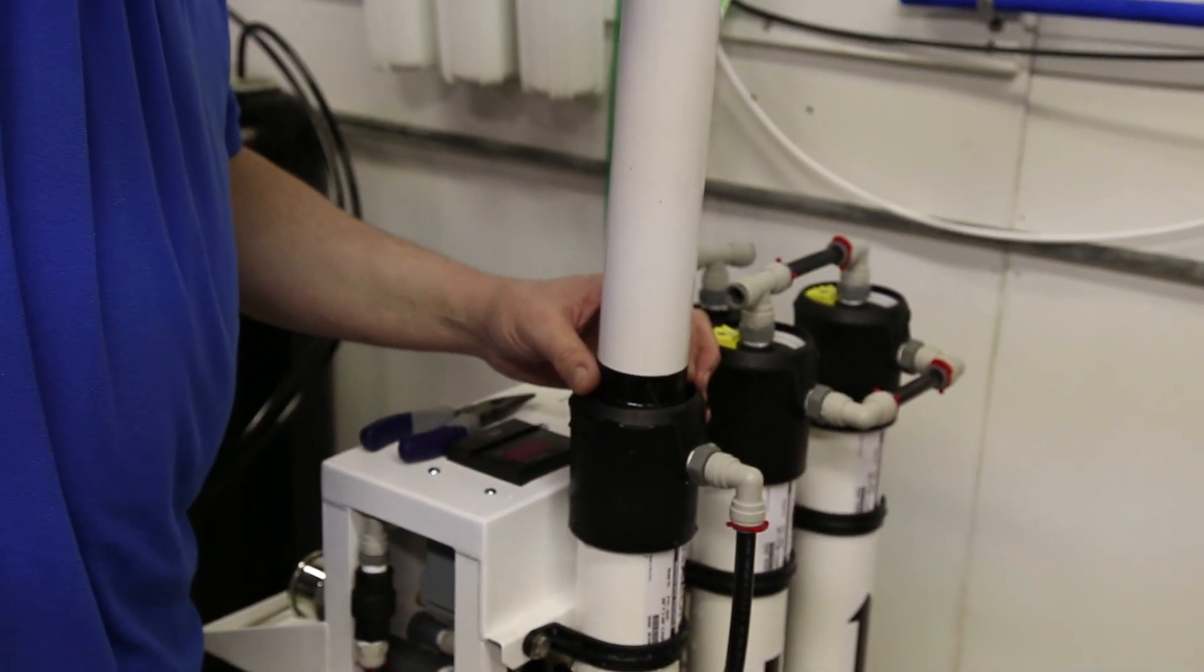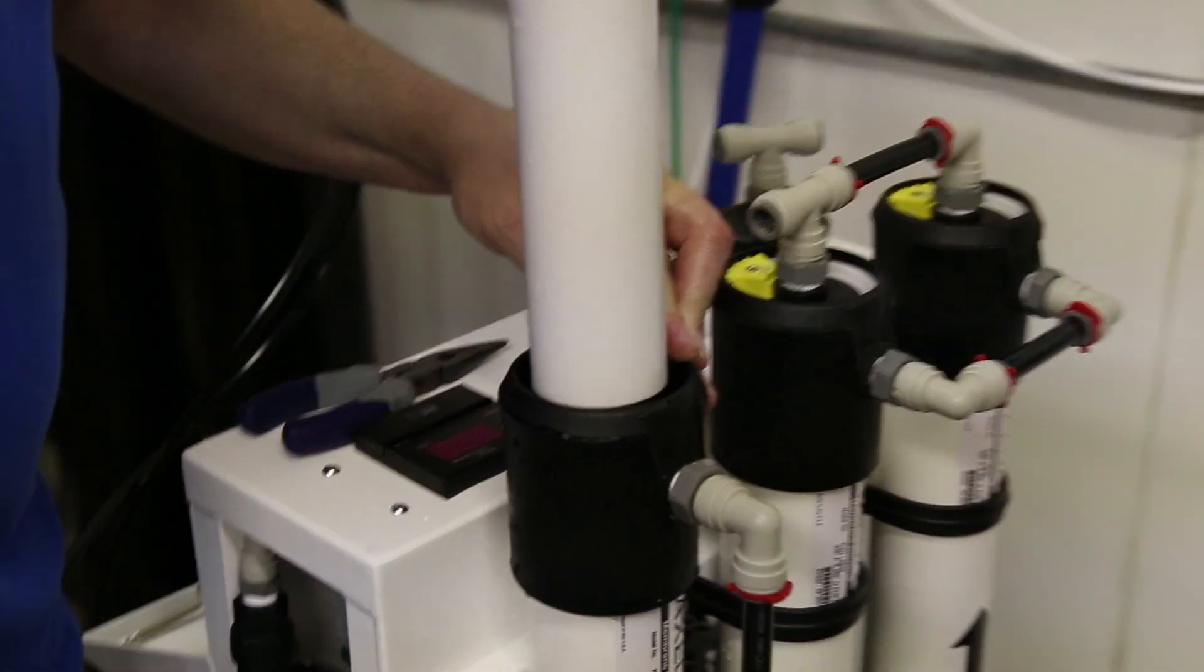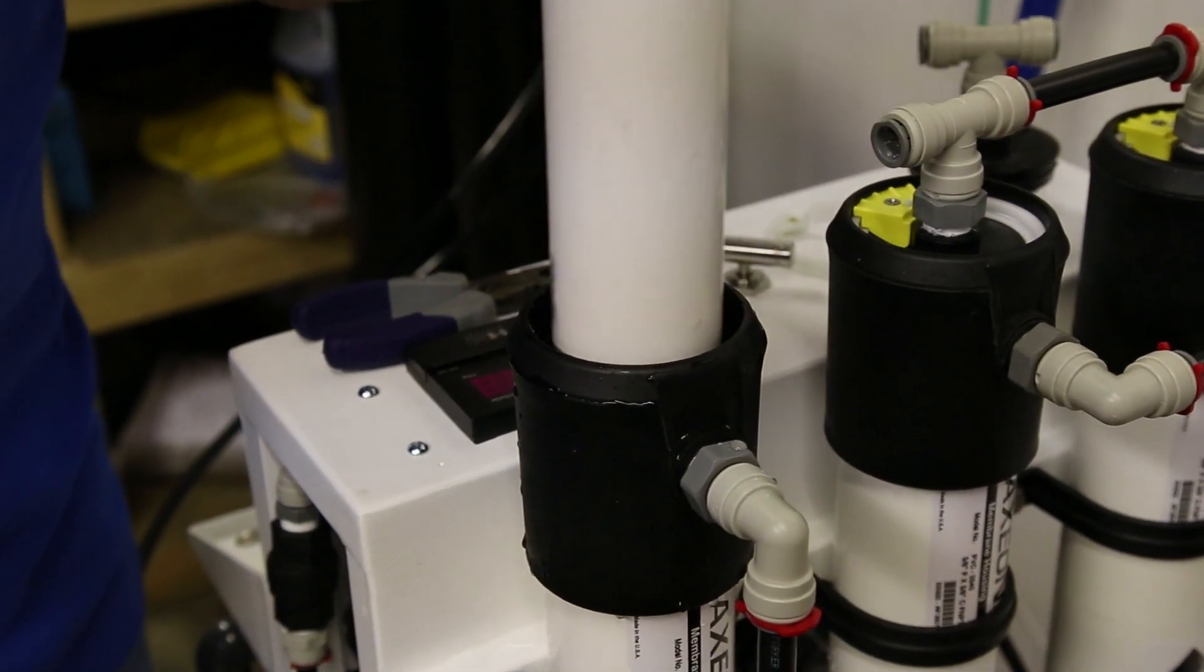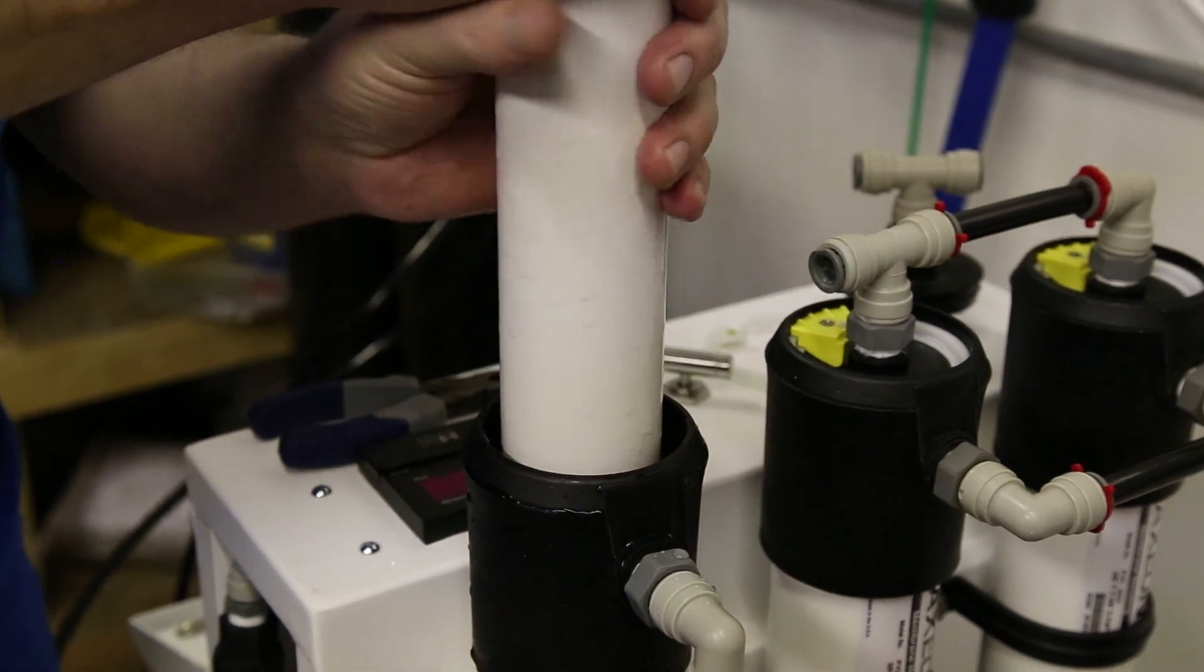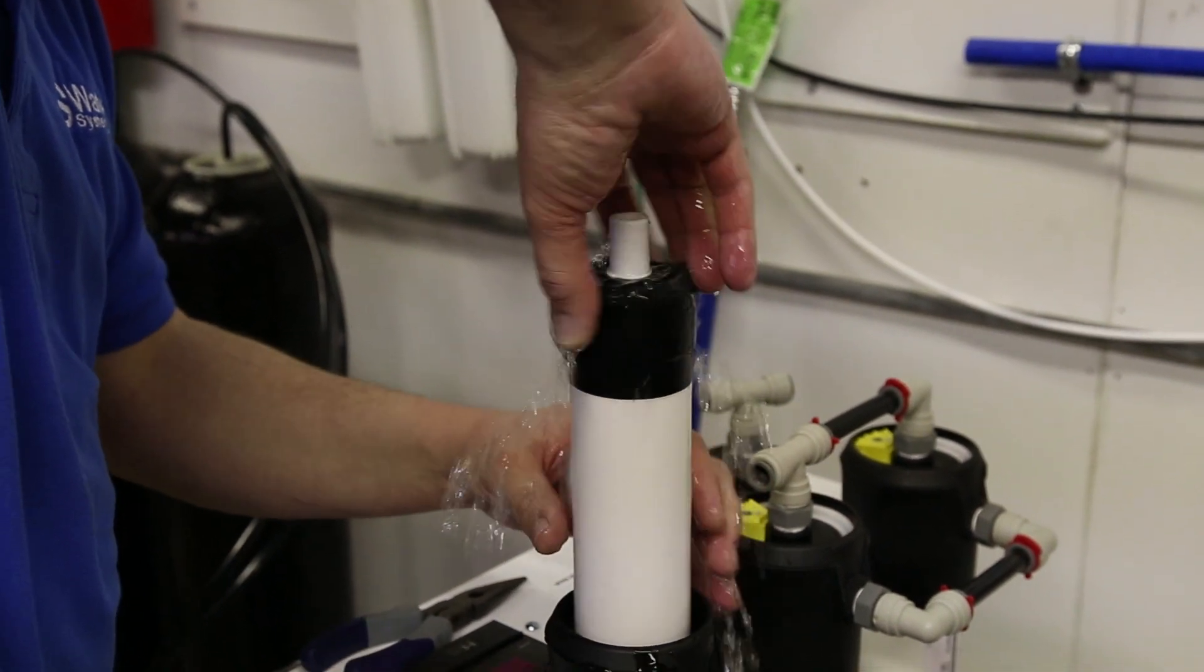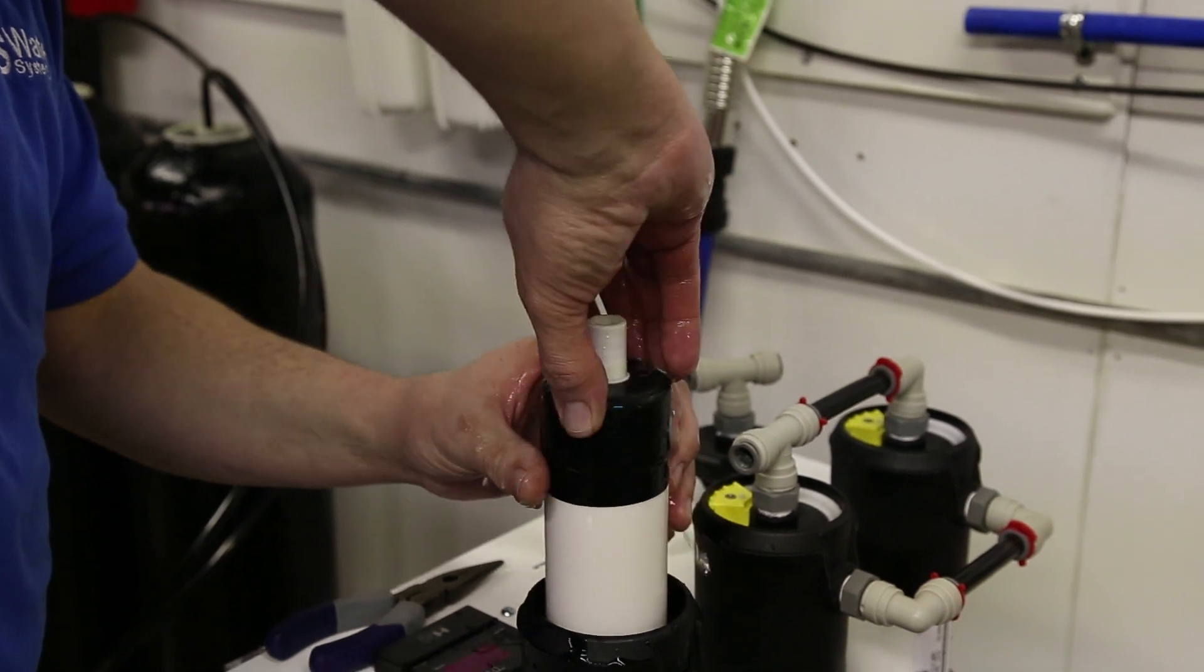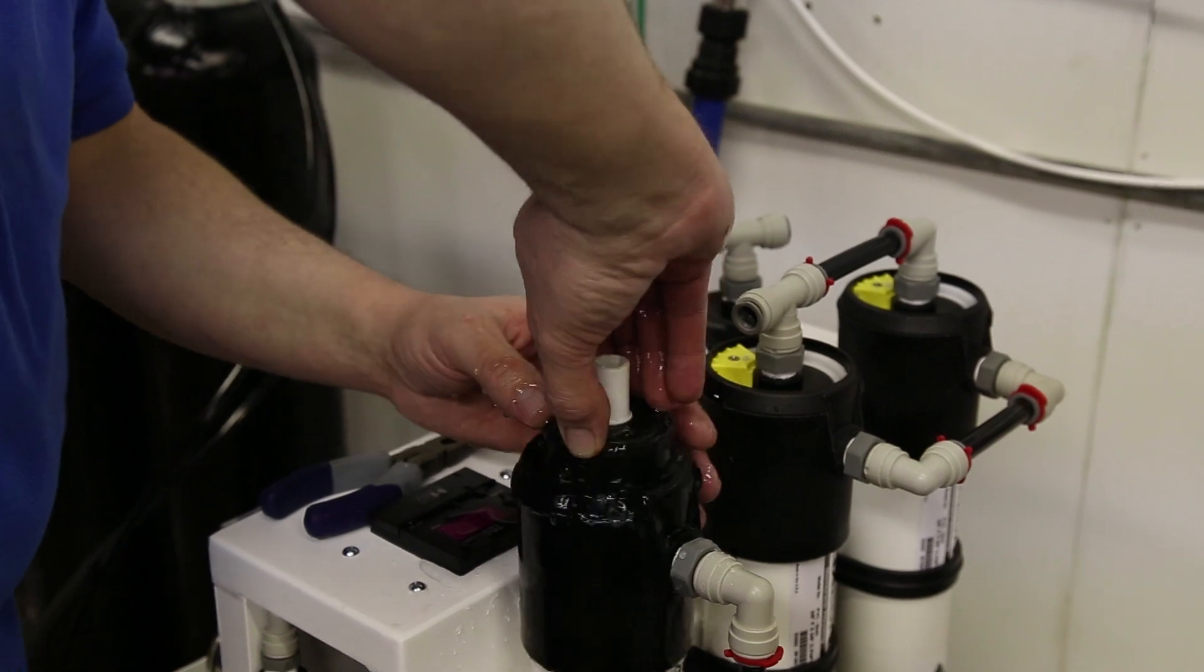If you look at the membrane housing, you can see the arrow pointing up, so that means it's being fed from the bottom, so the skirt seal should be at the bottom. When you put these back in, if you force it too fast you can roll this seal out. Whenever I'm putting this one in, I try to do a little bit of a twist action to get it started.